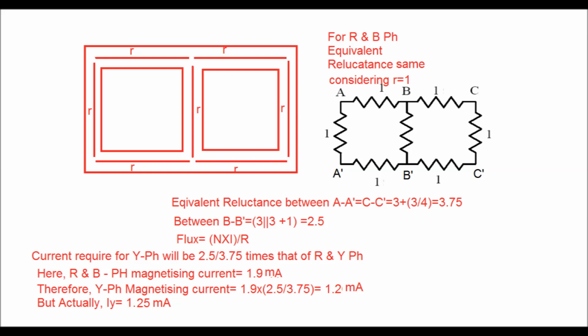Now a diagram has been shown with the reluctance of each section of the core as R. For calculating the reluctance for each limb, it is shown in this diagram. For red phase, the equivalent reluctance is between A to A dash. For yellow phase, the equivalent reluctance is between B to B dash, and for blue phase it is between C to C dash.